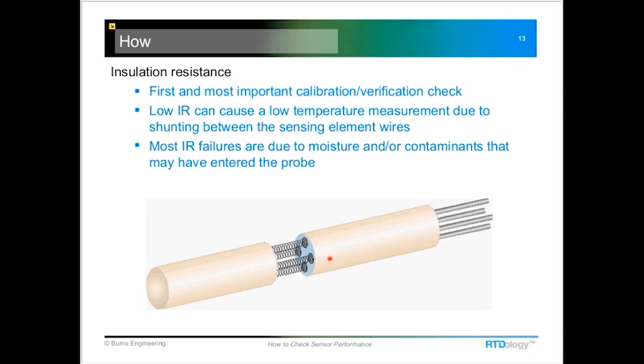If we do have moisture in there, we can note that by a low insulation resistance reading, and the moisture or contaminants can cause shunting between these coils and a low resistance reading. Because electricity always wants to take the path of least resistance, and sometimes moisture or contaminants can be that path, it's not going to go through the platinum wire and give us a good, accurate resistance and therefore temperature measurement. And probably 98 or more percent of insulation resistance issues are caused by moisture getting inside the probe.